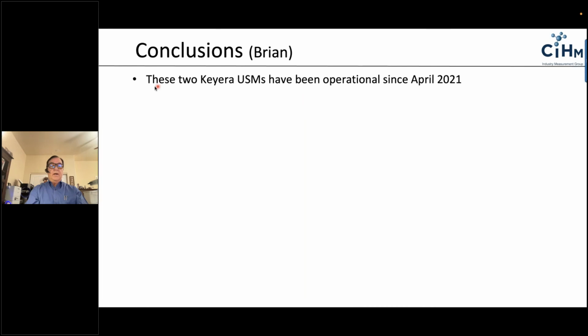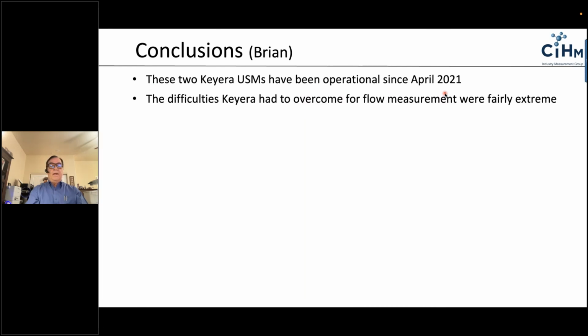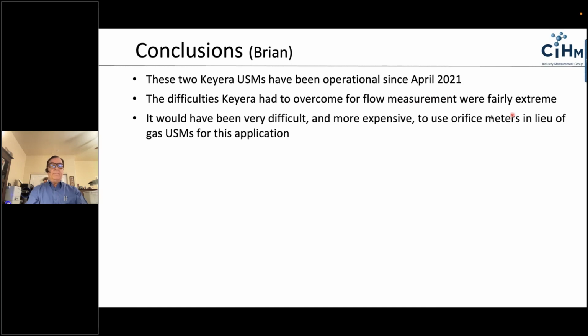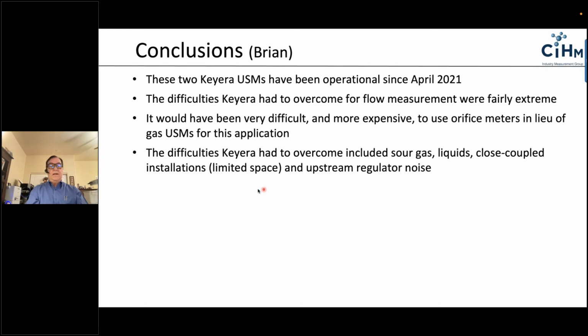So in conclusion, these 2 meters have been operational since April of 2021. The difficulties they had to overcome for flow measurement were fairly extreme. In this case, it would have been very difficult and much more expensive to use orifice meters in lieu of ultrasonic meters in this application. The difficulties Keyera had to overcome include the sour gas that we talked about, liquids occasionally coming through on the inlet carryover, close coupled installation due to the limited space, and of course the upstream regulator noise.